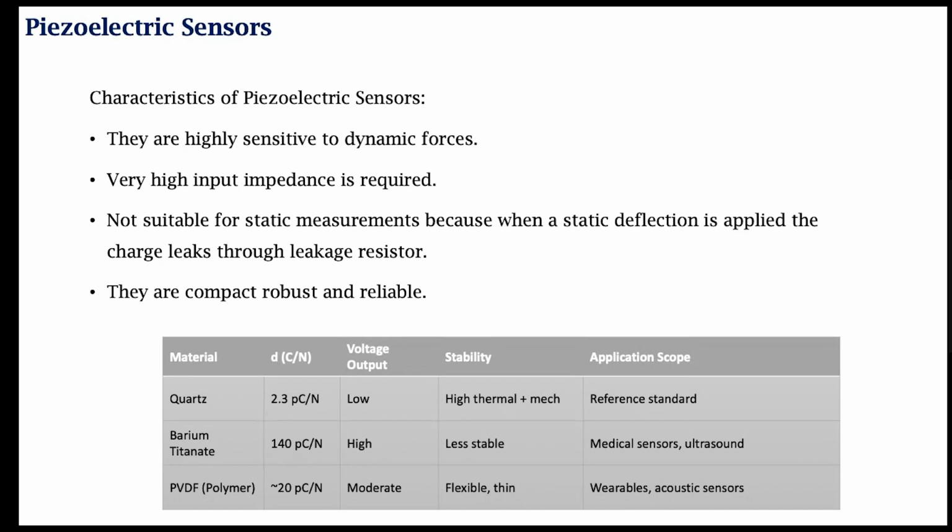Quite often, they are also used as catheter tip sensors to measure pressure waves inside the heart chamber, for example, inside the arteries, providing relatively highly accurate and high fidelity data of the heart function. And also to measure respiratory changes, subtle changes in chest wall movements, for example.